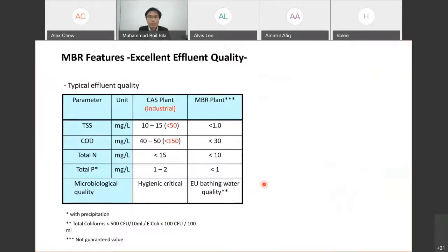Okay, so how good is the effluent quality of MBR compared to the CAS? This example I take from a report from Toray. So as you can see here, TSS for CAS can go from 10 to 15 if this is for domestic; for industry it can go up to 50. COD level normally for domestic we can achieve 40 to 50, but for industry it can go up to 150. And for all of these parameters, you see in MBR, they are much lower.